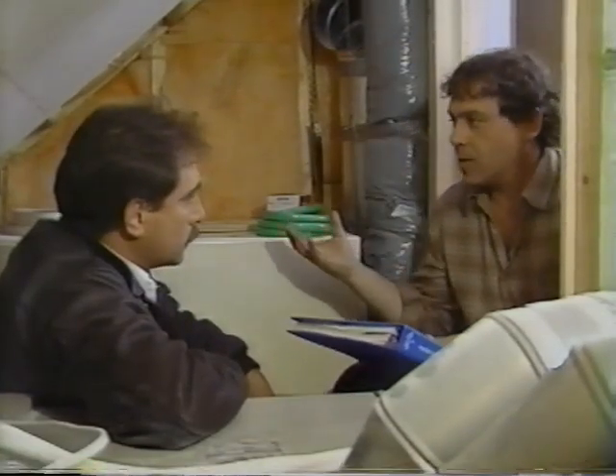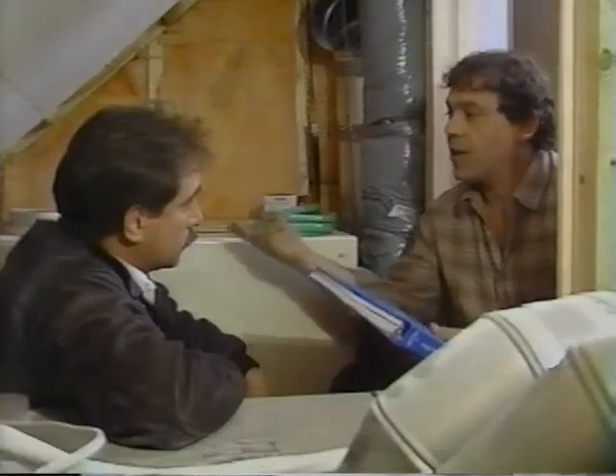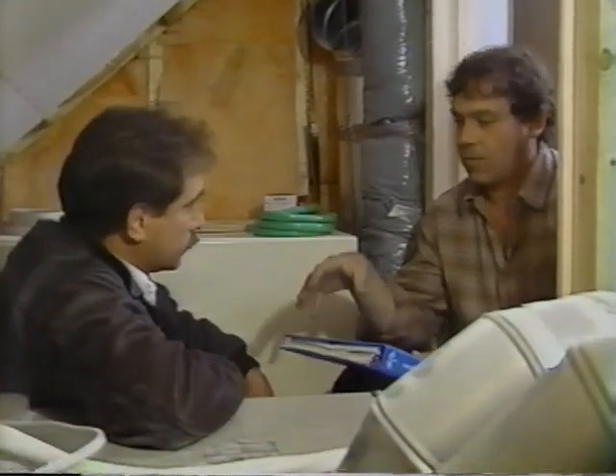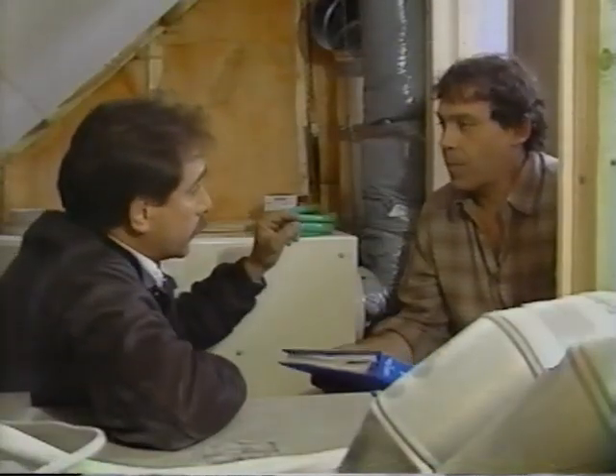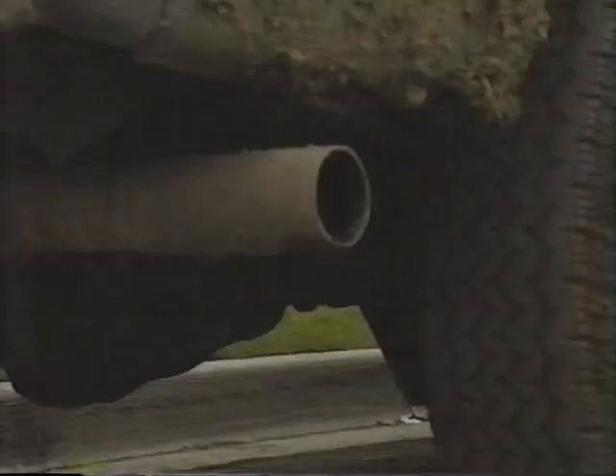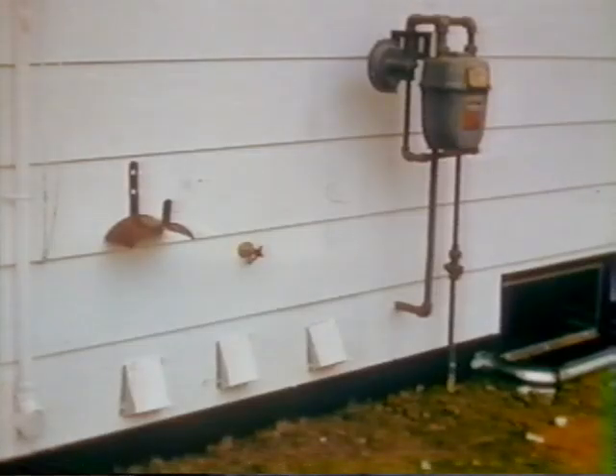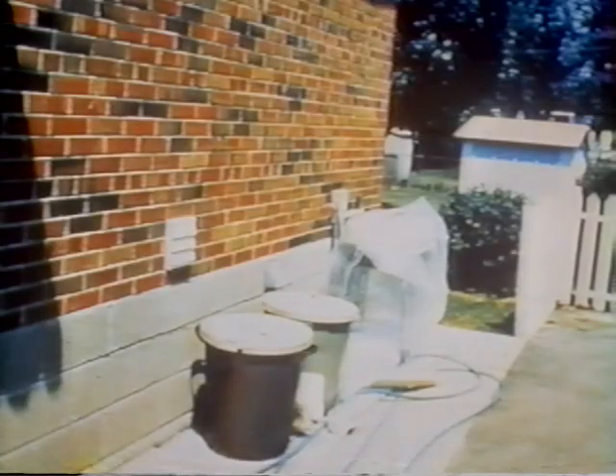Okay. Now, as far as the exhausts from the house go, you want to pick up the air in places where pollutants are created, like the bathroom, the kitchen, and the book even suggests the basement workshop. As far as the fresh air intake from outside, it's got to be in a place where it actually picks up fresh air, like not right where the tailpipe of the car is when you run it for 5 minutes in the morning. A really important point. In fact, the exhaust fumes from the car are very dangerous. You also have gas meters, you have oil filler pipes, and of course the thing has to be located away from any area where you might have garbage, and you don't want it covered by snow either.